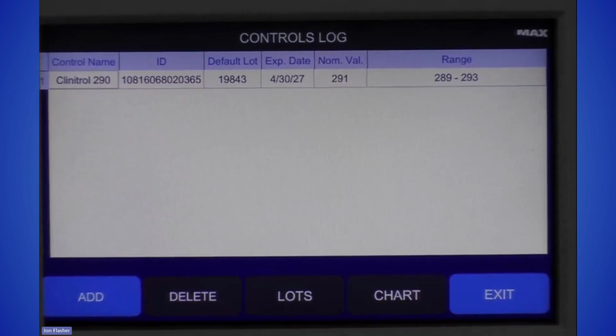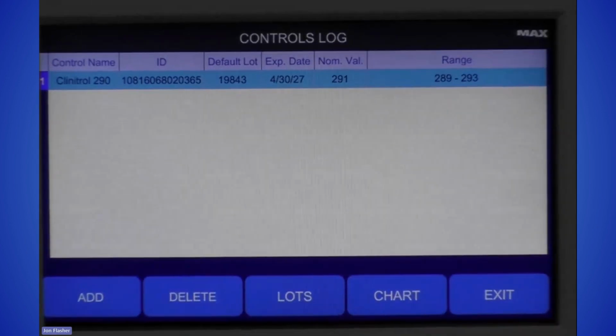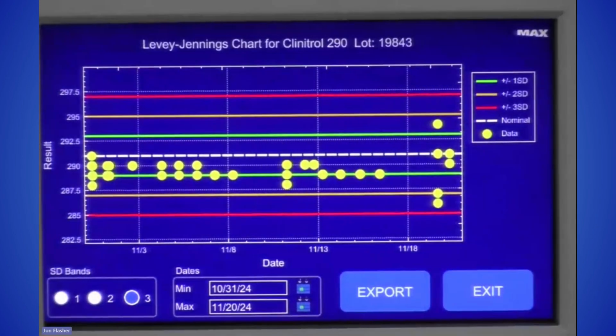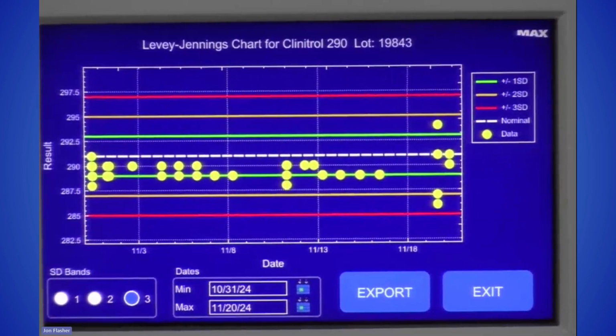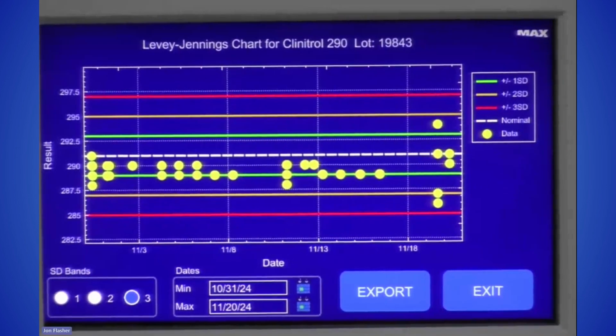But if I wanted to click on this, if I wanted to see a Levey-Jennings plot of all of the control runs that I've run as part of this lot of Clinitrol 290, you can just hit this little chart button. And then you can see the plot right there. And then based on your standard deviation that you set for the acceptability of results of your control runs, you can actually see which bands correspond with where your results actually lie. So just an example of what you can see there. You can also see a date range that you can pre-program to see, okay, since this date, how have I been performing from a QC perspective?